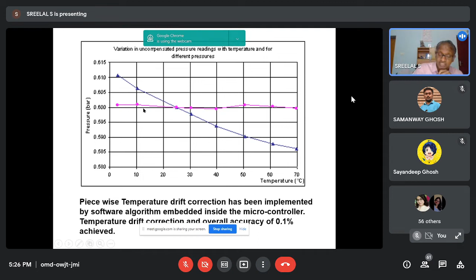So the output voltage depends not only on the input pressure but also on a parasitic component such as temperature. For an ideal sensor, we want to make the reading insensitive to temperature. So what we do is called temperature compensation, which is data processing done by the microcontroller inside the smart sensor. After that is done, the pressure reading is constant with respect to temperature. That is, the variation of the reading with respect to temperature is nullified by the compensation scheme.